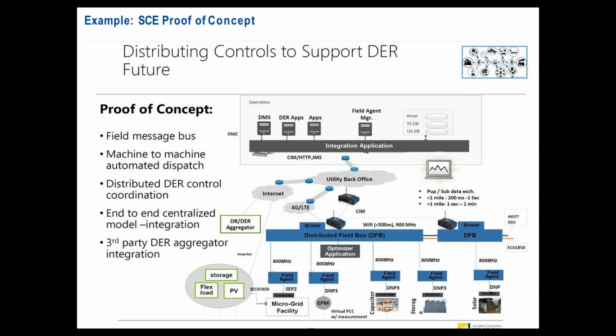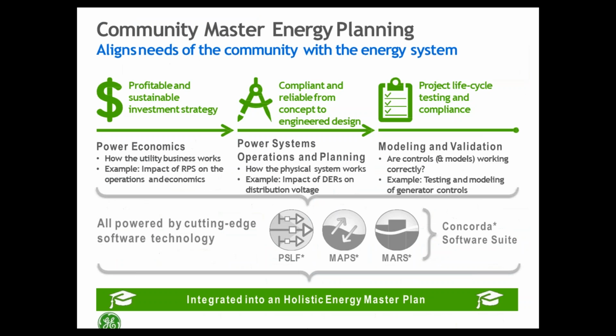And in this application, we did volt-VAR control with these various assets. But the architecture we developed here is so inexpensive, you could bring this design down even to the home level. These radios are very inexpensive and can be installed very quickly and cheaply. So this is one good example of a pilot project we did with SCE that reflects the philosophy of getting visibility, control, and optimization out there in a very low-cost way. Next slide, please.